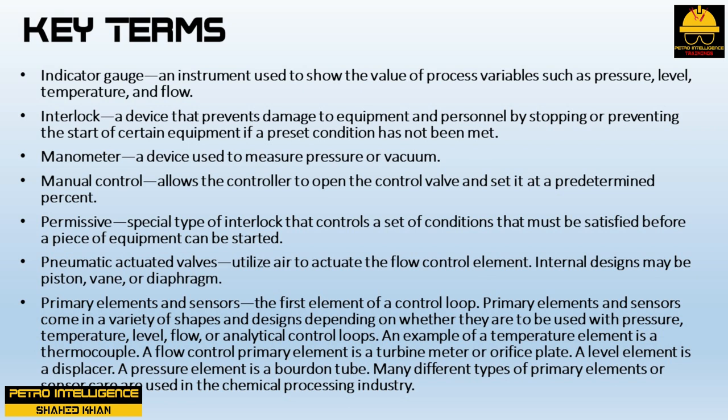An indicator gauge is an instrument used to show the value of process variables such as pressure, level, temperature, and flow. An interlock is a device that prevents damage to equipment and personnel by stopping or preventing the start of certain equipment if a preset condition has not been met. A manometer is a device used to measure pressure or vacuum. Manual control allows the controller to open the control valve and set it at a predetermined percent. A permissive is a special type of interlock that controls a set of conditions that must be satisfied before a piece of equipment can be started.